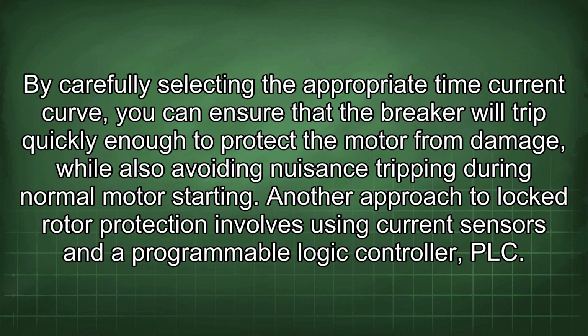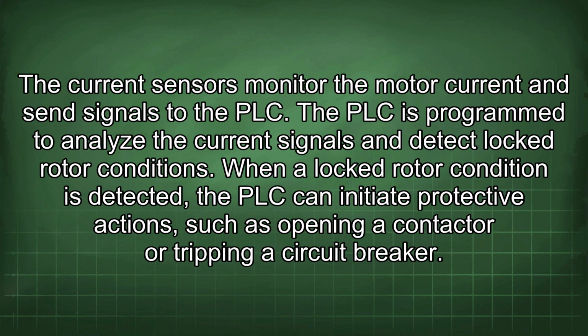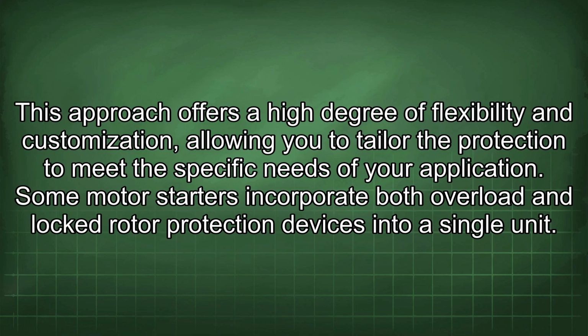Another approach to locked rotor protection involves using current sensors and a programmable logic controller (PLC). The current sensors monitor the motor current and send signals to the PLC. The PLC is programmed to analyze the current signals and detect locked rotor conditions. When a locked rotor condition is detected, the PLC can initiate protective actions, such as opening a contactor or tripping a circuit breaker. This approach offers a high degree of flexibility and customization, allowing you to tailor the protection to meet the specific needs of your application.